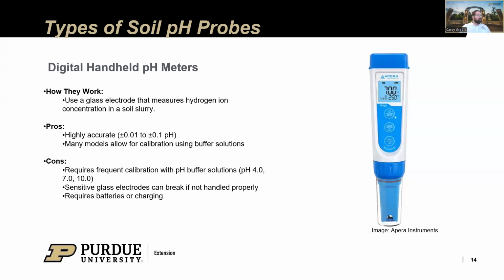On a lot of these units, the probes are replaceable, so these digital probes are going to be a little bit more expensive. But the benefit is you have the option to replace just the probe and not the entire unit. It's more of an investment, but you're getting more accuracy and that calibration effect. You just have to pay a little more attention to the unit.